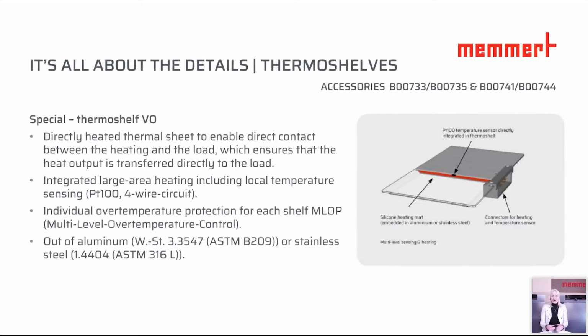Let's have also a look at the thermoshelf of our vacuum oven. When we consider the thermoshelf of the vacuum oven, it is outstanding that we have the sensor directly placed on the shelf, because each shelf is controlled individually, and furthermore there is also protection on each shelf. We have the heating all over the shelf, and it's a direct heating, so that means we heat up the shelf in order to transport the heat to the samples, which is for a fast heating up and for very good uniformity. We have here an aluminium oxidized shelf according to ASTM B209. This is for fast heating up and most precise uniformity.